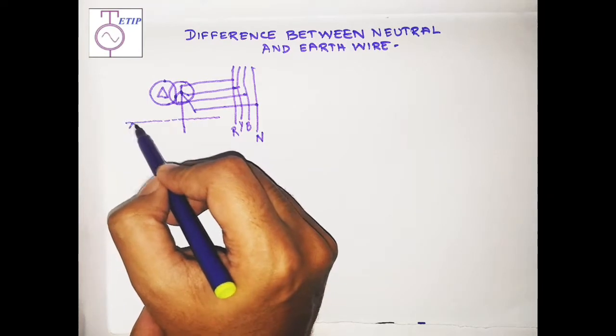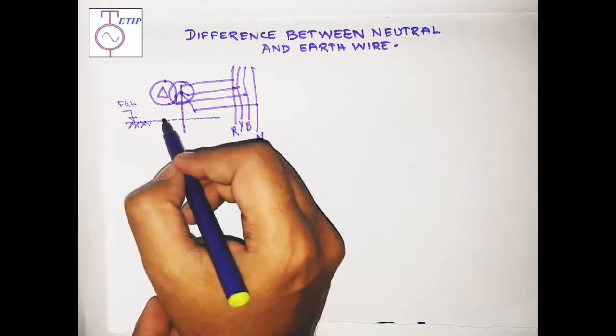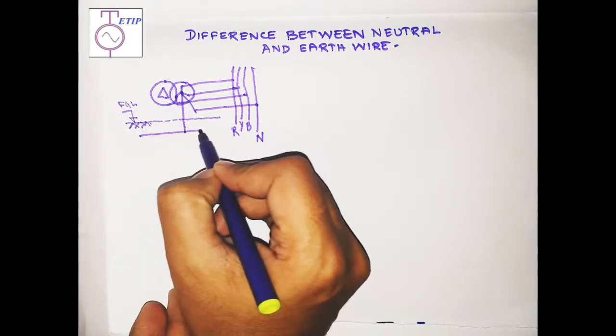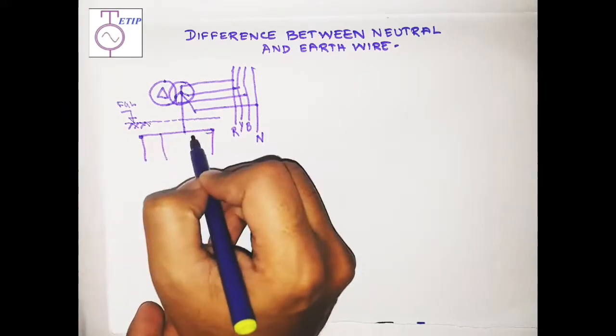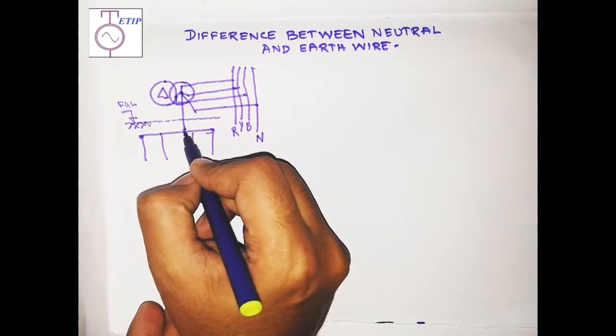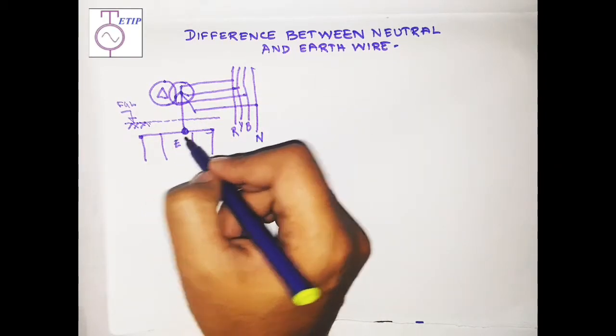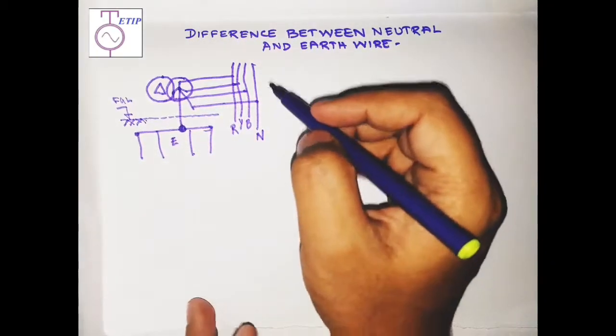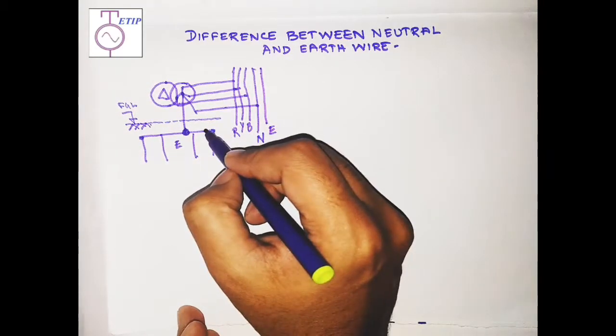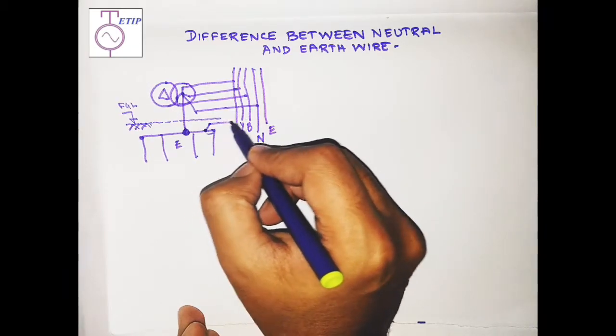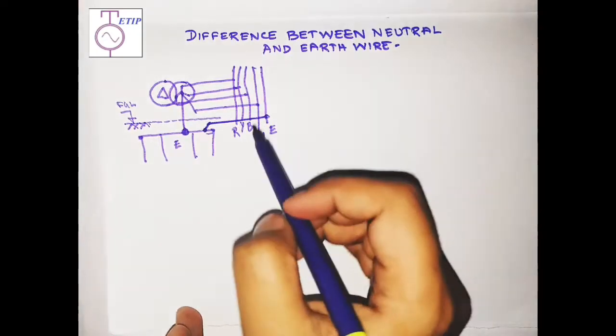This neutral is earthed at the substation end. Below the finished ground level, ground conductors and electrodes are laid, and the neutral is connected to these ground conductors. From here the earthing conductor is generated. In the switchgear there is another bus called the earth bus, which is connected to the substation ground mat.